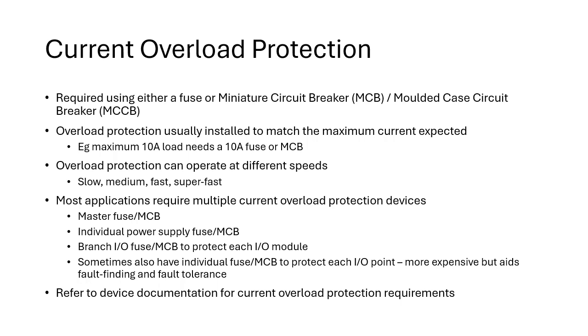So if we know there's a maximum 10 amp load, we would choose a 10 amp fuse or a 10 amp molded case circuit breaker, MCCB, or miniature circuit breaker, MCB, depending on your terminology. Now what you might need to look at is, the maximum 10 amp load might be a sustained 10 amps, but there might be a possibility of an inrush when you first start up. So that 10 amp load might be 15 amps for a few milliseconds when you first enable that load.